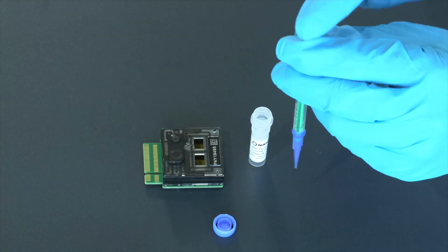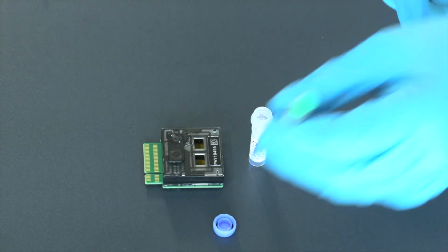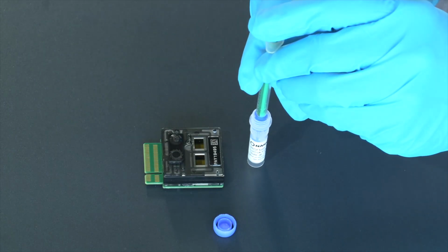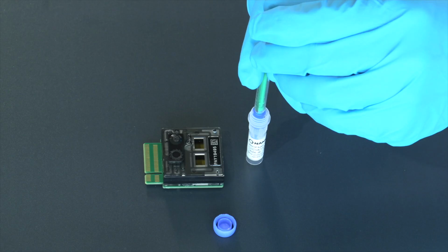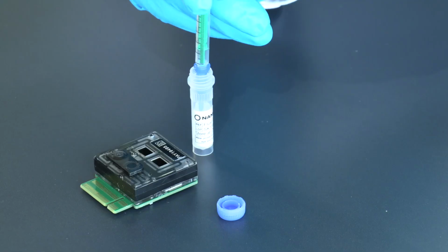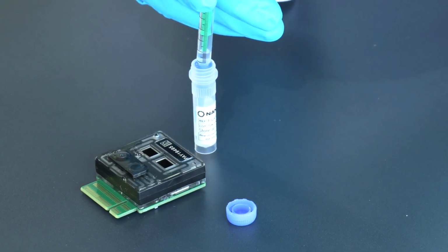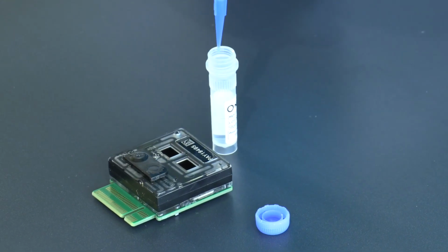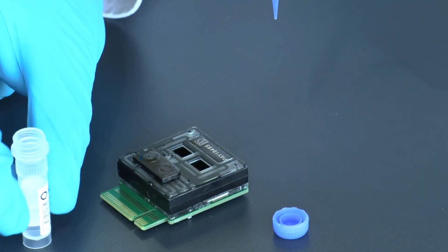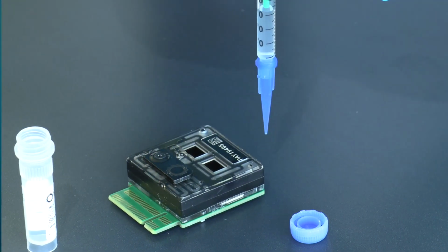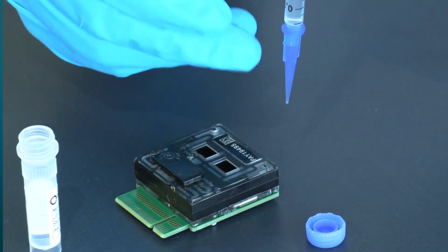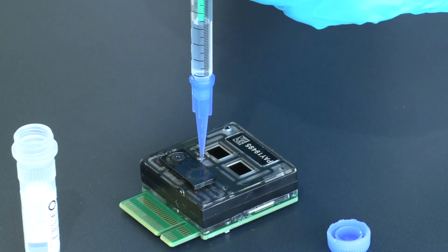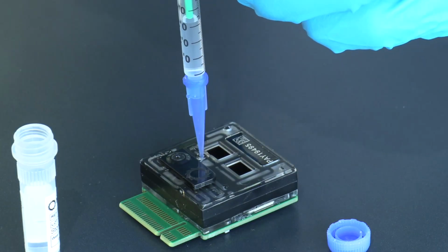Before we do that, let's make sure that our plunger is at the very bottom of the syringe. Insert it into the tube vertically, and very carefully and gradually let the widest part of the plunger reach 0.5 milliliter mark. Once we reach that, we can once again take the syringe out of the tube.